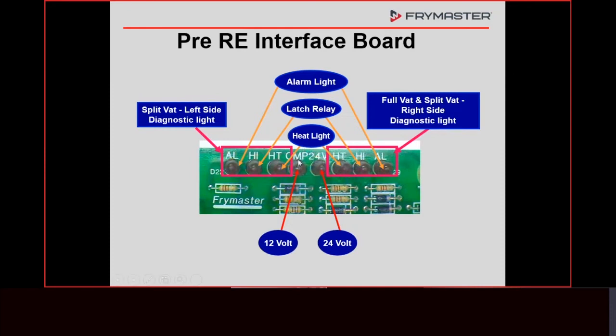Technicians don't use those indicator lights, we use meters. If this light comes on, that means you have voltage coming to that board, guaranteed we have 1 or 2, whatever LED it takes. I've heard both, but the thing is, it doesn't tell you if you have 24 volts. A meter will tell you how many volts you have. But again, they're a good indicator.